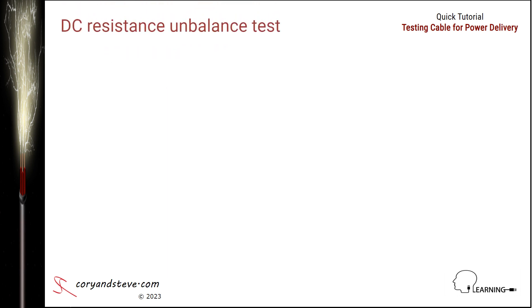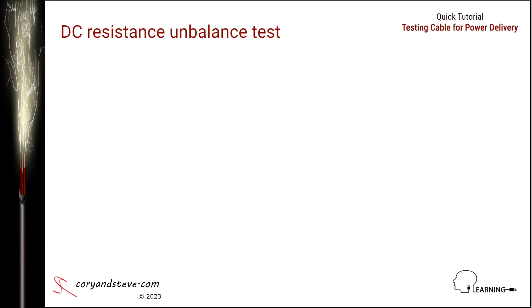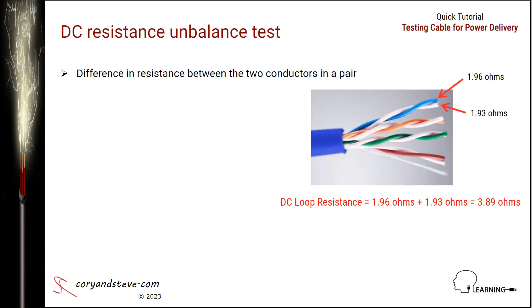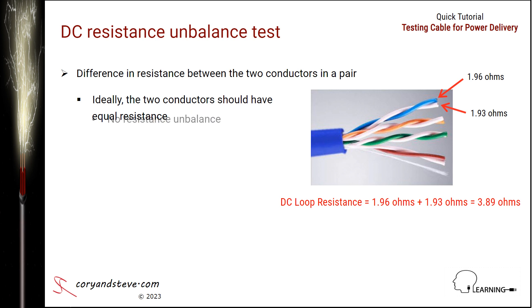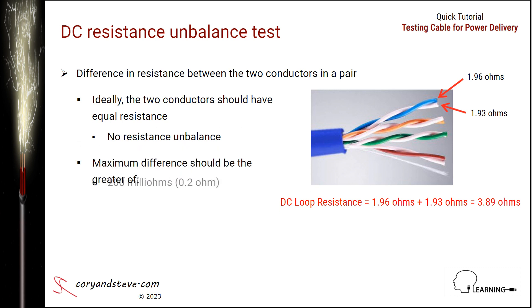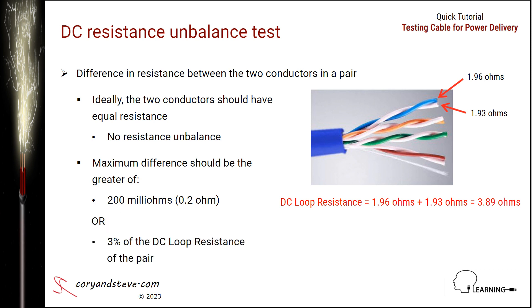Next we have DC resistance unbalance, the second of the three DC resistance tests. DC resistance unbalance for a pair is calculated as the difference in resistance between the two conductors in a pair — recall that DC loop resistance was the sum. Ideally, the two conductors should have equal resistance and there should be zero difference or no resistance unbalance in any of the four pairs. But in the worst case, the difference should be no greater than 200 milliohms or 3% of the DC loop resistance of the pair, whichever is greater.